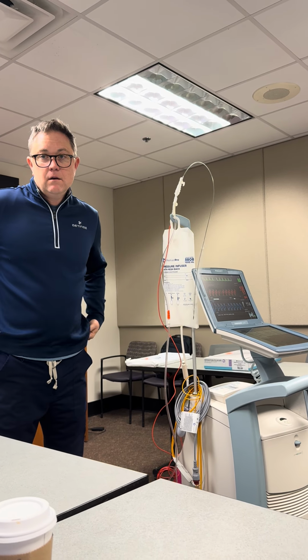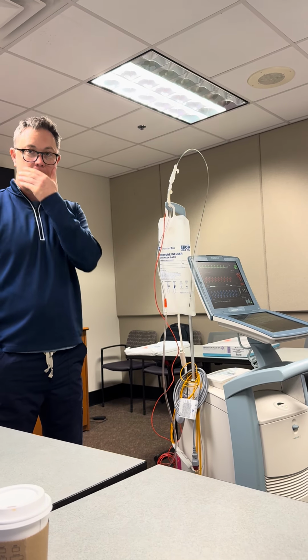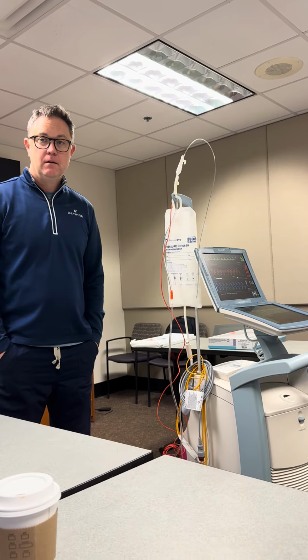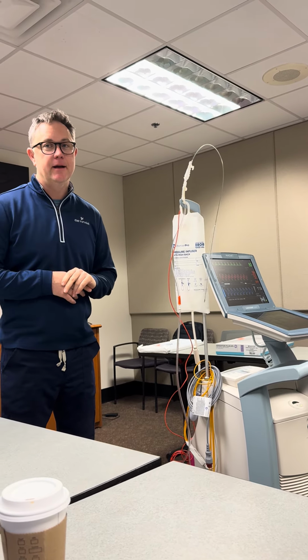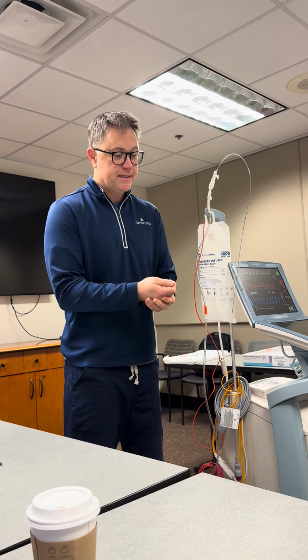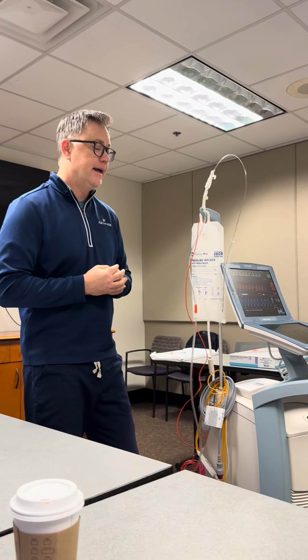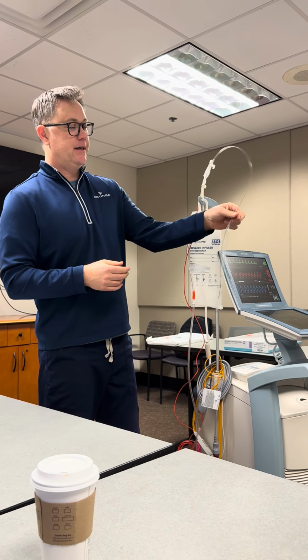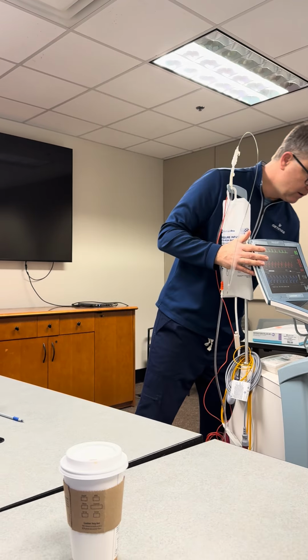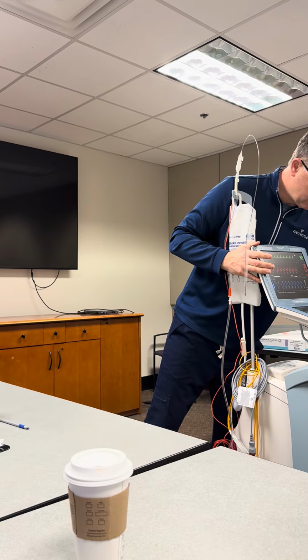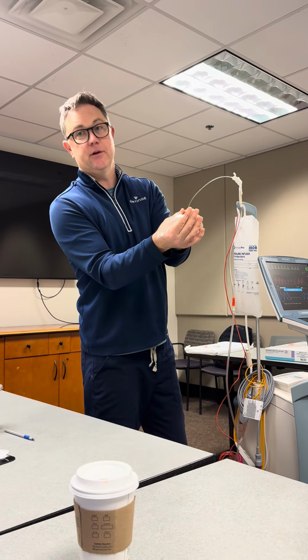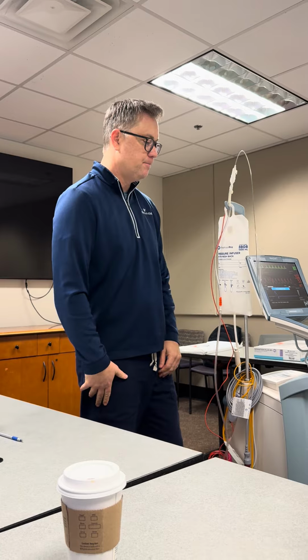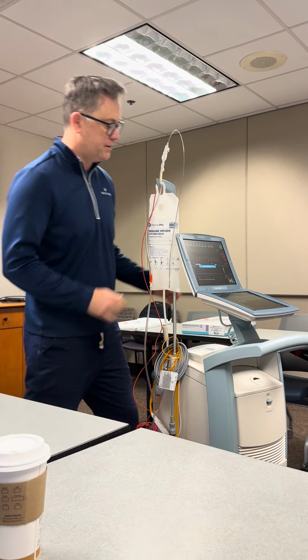If you have a ruptured balloon, what's the likelihood that you'll be able to remove that and leave your sheath in place? No, that's not recommended, because of shear. So what we'll ask you to do when you're removing it is pull back until you get tension, until you feel that catheter come back to the sheath, and then pull them both out as one unit. It's not recommended that you leave a sheath in, because this thing has been inflating and deflating, and when you pull it back, you could shear it off when you get back to the sheath. That's why we pull it back until you get tension and then pull them both out as one unit.